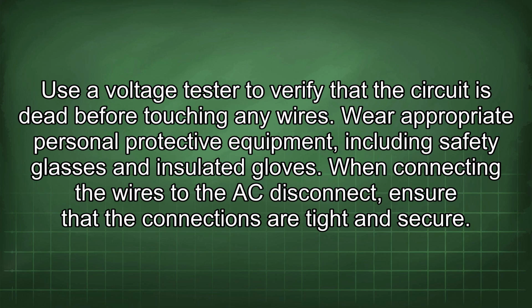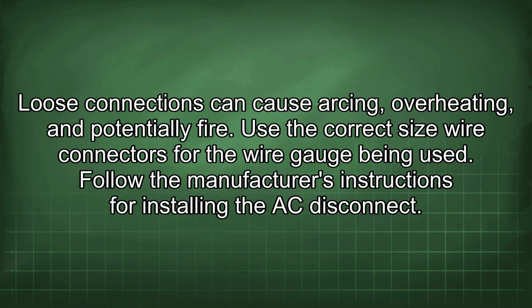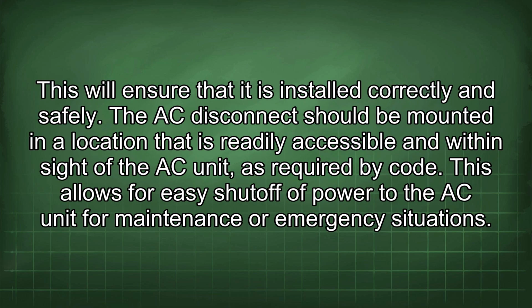When connecting the wires to the AC disconnect, ensure that the connections are tight and secure. Loose connections can cause arcing, overheating, and potentially fire. Use the correct size wire connectors for the wire gauge being used. Follow the manufacturer's instructions for installing the AC disconnect. This will ensure that it is installed correctly and safely.